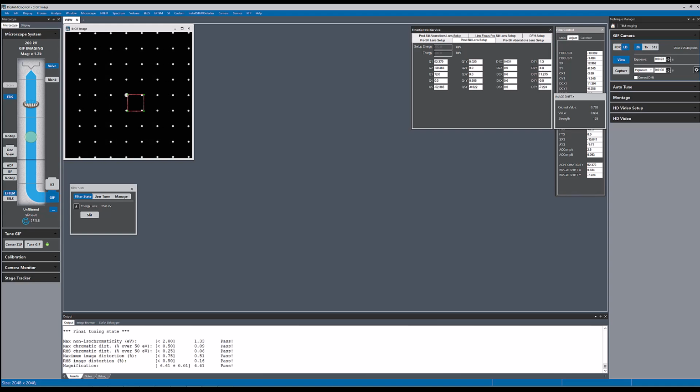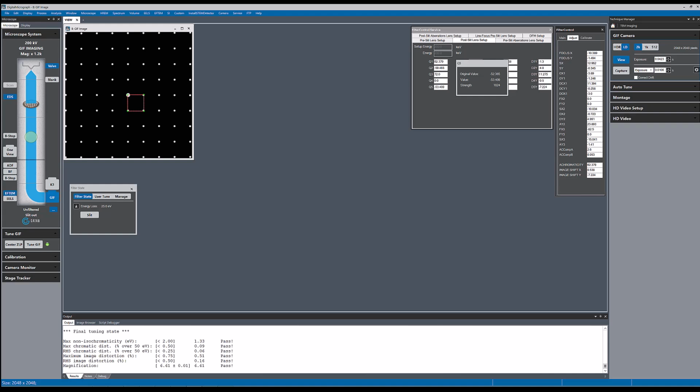After the image shift, we need to correct the magnification. That's done with some multipole lenses. You can see if I change this lens, it changes the magnification, or the projected size, of the mask pattern.